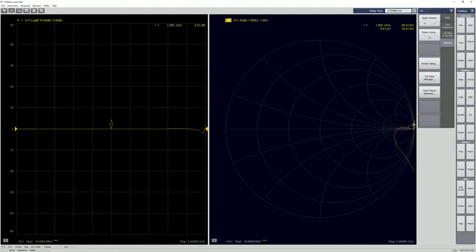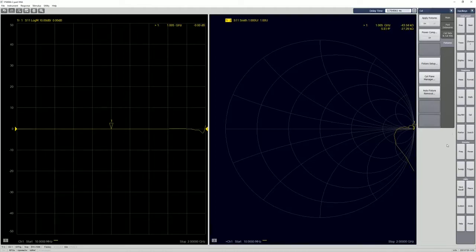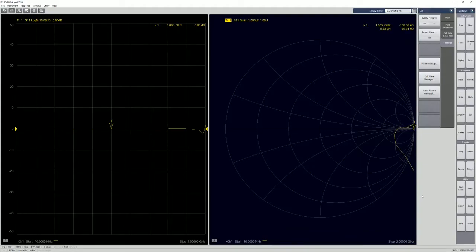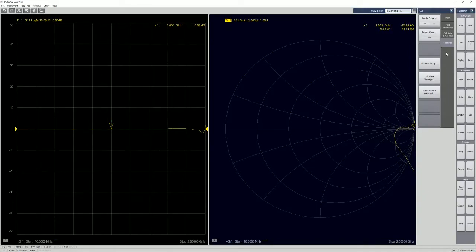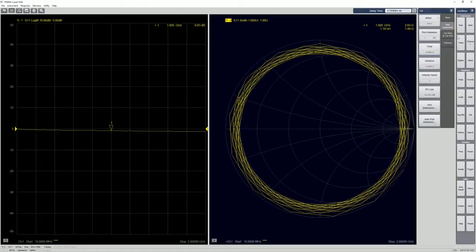So according to the help file for this VNA, it's recommended to set the stop frequency at least 10% more than what you want to measure. For example, I want to measure on my device under test up to 2GHz. So it's recommended to put a stop frequency to additional 10%, 2.2GHz. So with that, let's turn this off again.